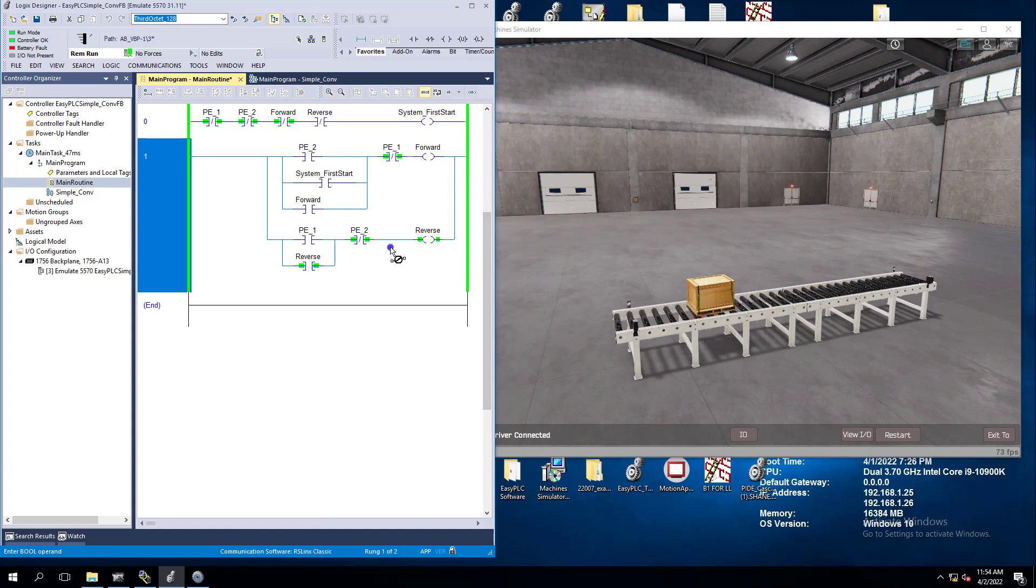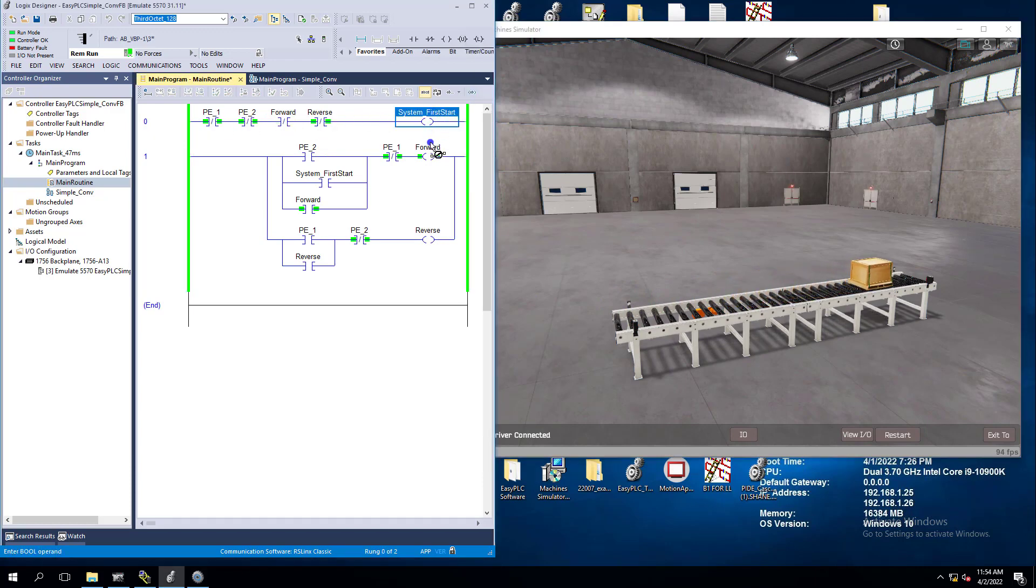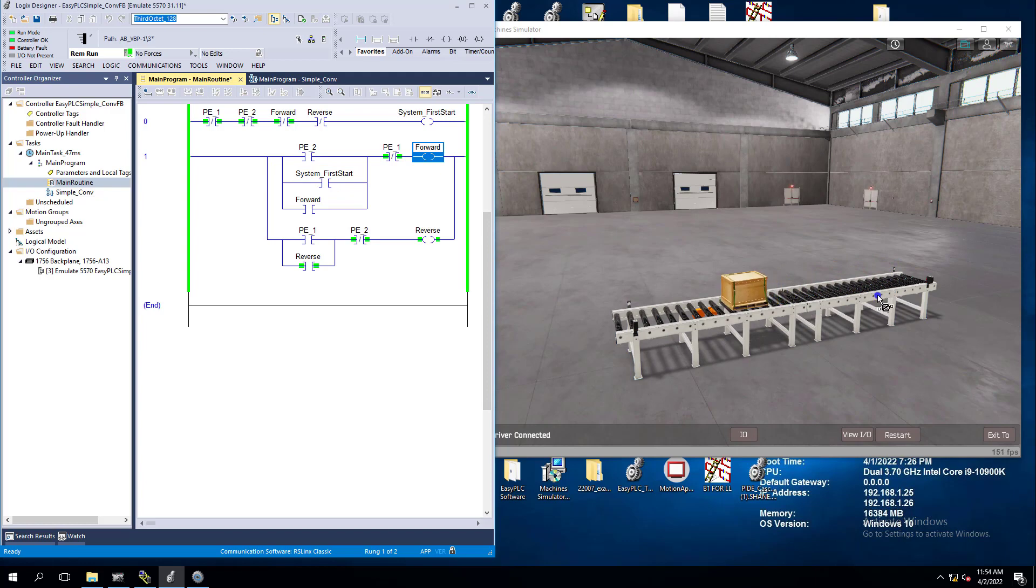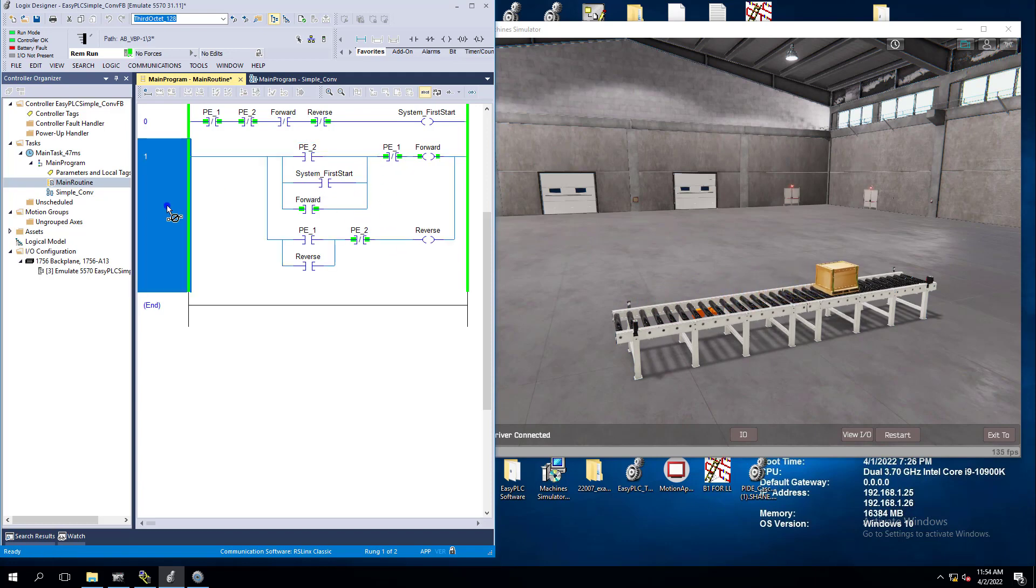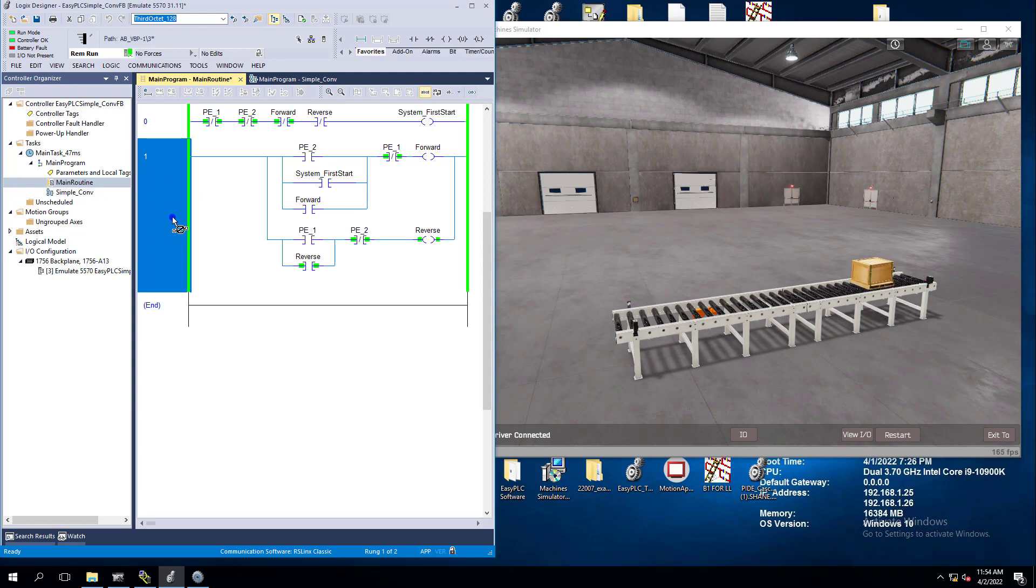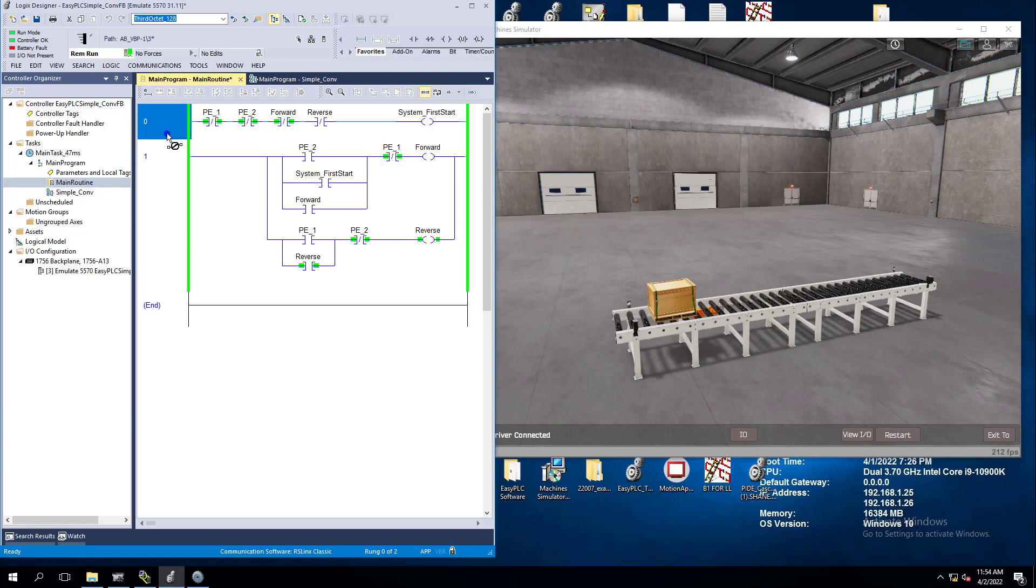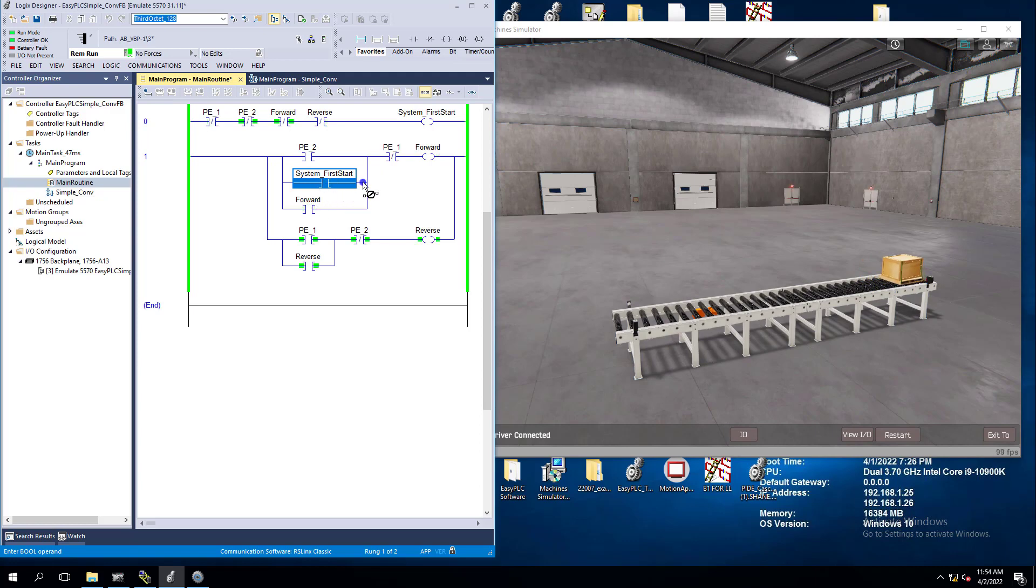So you can easily see the logic. What I'm doing is I'm basically saying if nothing is made in the very beginning, I'm going to initiate the first system start, which the system starts going to move it in forward and the forward bit is going to take it in the opposite direction and work off the photo eyes. The photo eyes will control, they will assume this next rung will then take over the actions. So basically the only time rung zero is active or controlling something is when the system is not active whatsoever. So it does give it a command to run forward after that, which is right here.